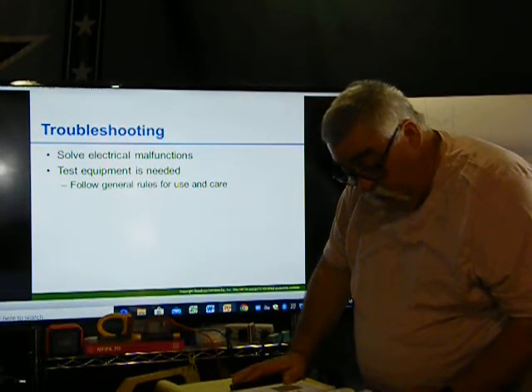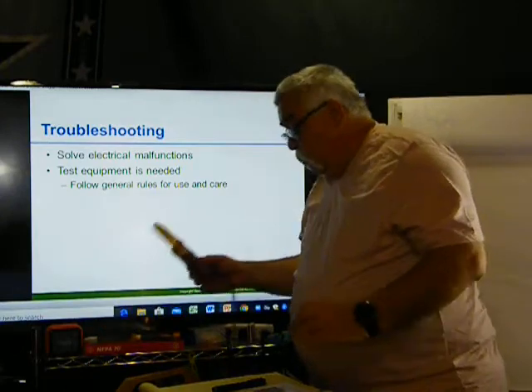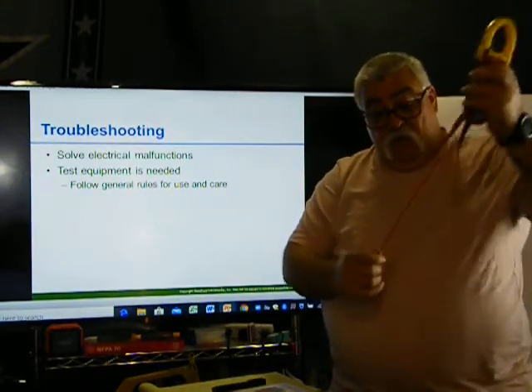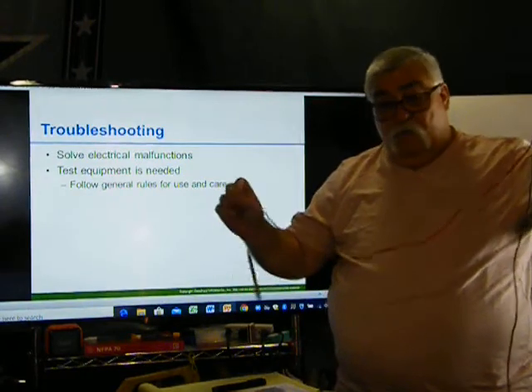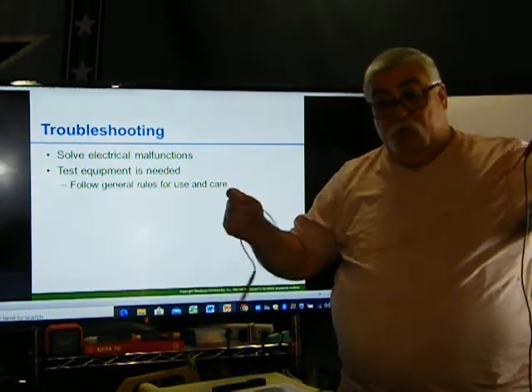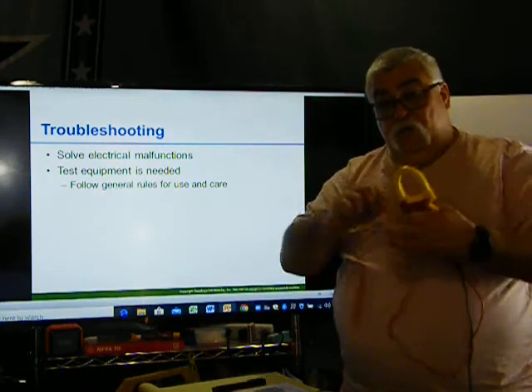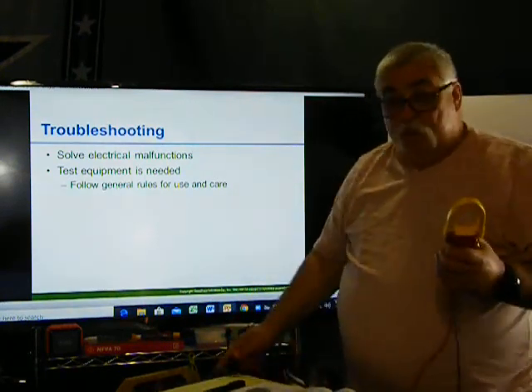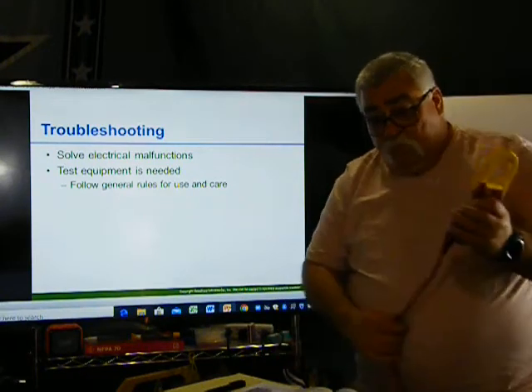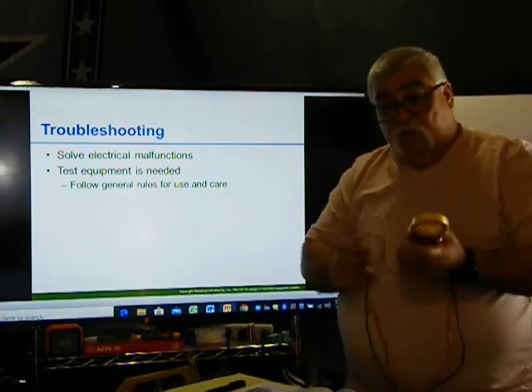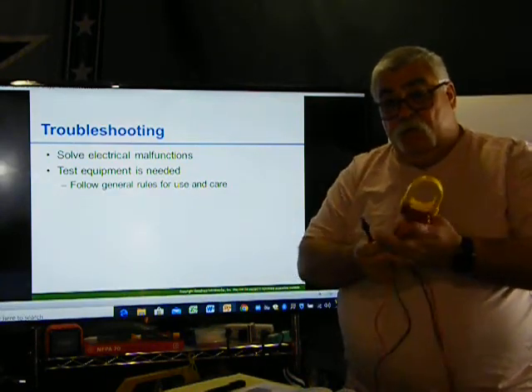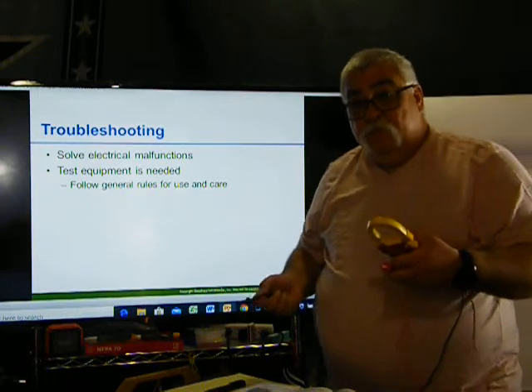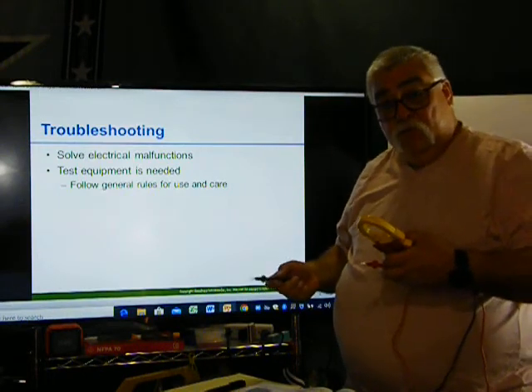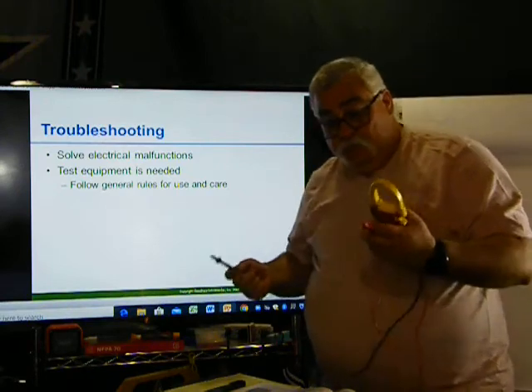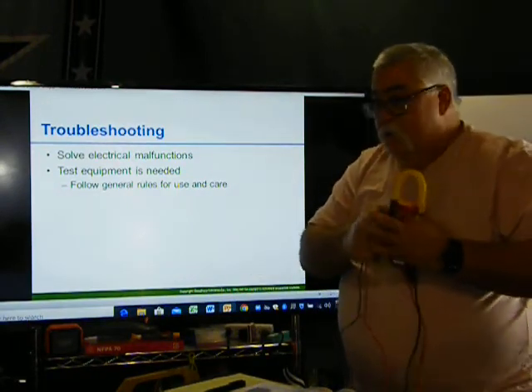Inspect insulation on test leads before and after use, looking carefully for any cuts, abrasions, or nicks. If you keep them locked up they're safe, but these can get brittle. The plastic can get brittle and start to break. The last thing you want is a nick. You pull it back, it goes over a sharp edge, you don't catch it and you don't inspect it, and all of a sudden you go to grab it to test something, and that area is nicked. Well, guess what? You're going to be that light bulb. What happens to a light bulb when it gets electricity? It gets lit up. So always test to make sure you don't get lit up.